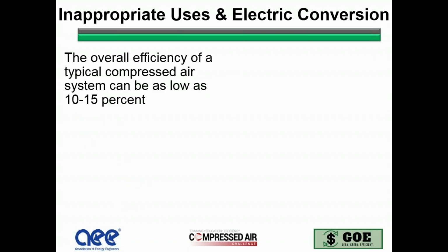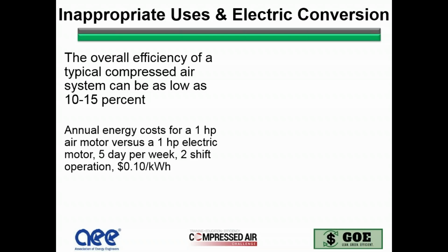Inappropriate uses. Inappropriate uses are really anything that you can do with electric technology. The most common one is anytime anybody's using an air motor, that can be looked at for using an electric motor. And why do we want to do that? Well, the overall efficiency of a typical air compressor can be as low as 10 to 15%.